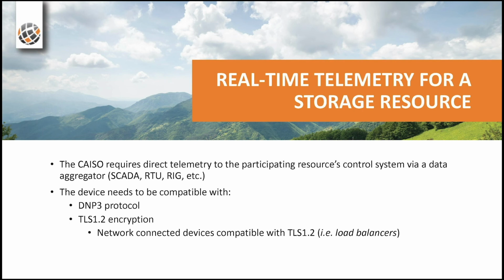But the majority of resources in the ISO's market use direct telemetry. The direct telemetry requirements are DNP3 protocol, with TLS 1.2 encryption wrapped around that DNP3 protocol. There are also network devices out there that can do the encryption between the ISO and the interconnection customer's firewall, and then on the interconnection customer side of the firewall, you can be in the clear with the DNP protocol and create your own direct telemetry device behind your load balancer, for example. There's plenty of SCADA systems, RTUs, and different types of devices that can talk DNP3.